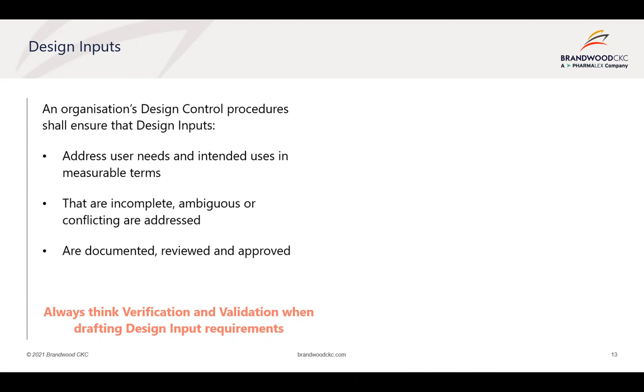So when you're documenting your design inputs, your design control process itself should ensure that your design inputs are written in such a way that they address the user's needs and intended uses in measurable terms. You want to make sure that they're written in a way that they're complete, non-ambiguous, and not conflicting. And all of those design inputs as well need to be documented, they should be reviewed, and they need to be approved.